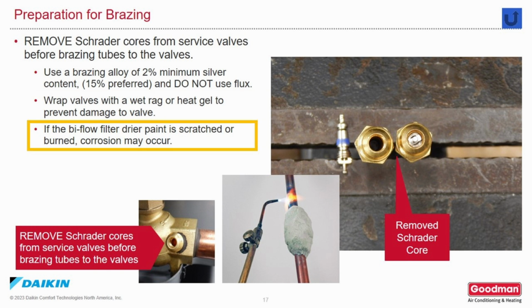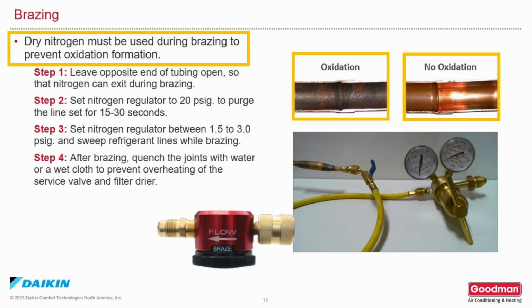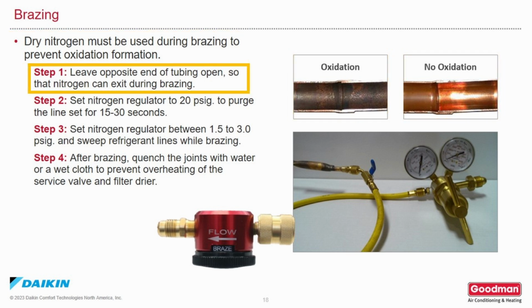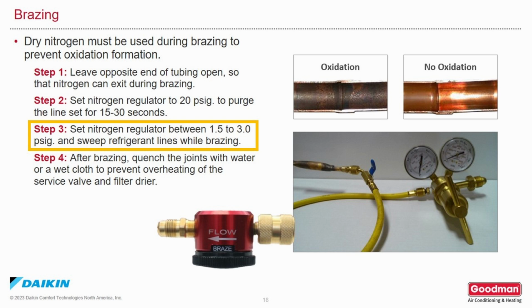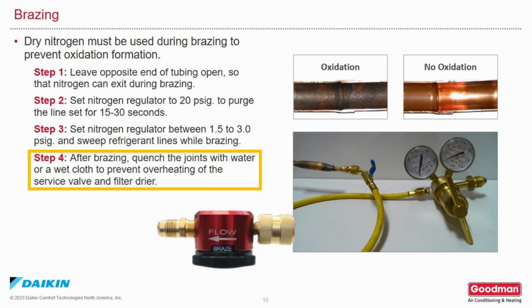If the biflow dryer paint is scratched or burned, corrosion may occur, rusting and causing a loss of integrity of the refrigeration system. You must use dry nitrogen while brazing to prevent oxidation from forming inside the pipe. Leave the opposite end of the tubing open so that the nitrogen can exit. Purge the line set for 15 to 30 seconds at about 20 psi. Then allow nitrogen to flow at 1.5 to 3 psi while brazing. Then cool the brazed joints with water or a wet cloth to prevent overheating the service valve and the filter dryer.